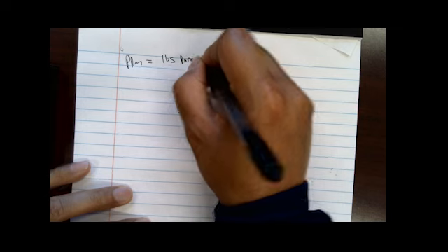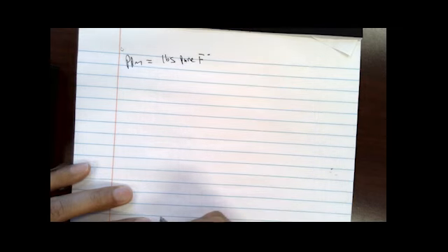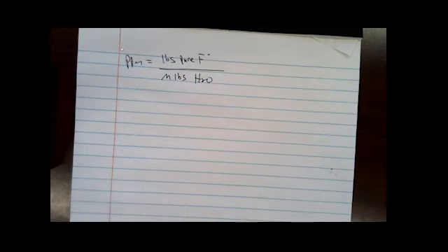Let's first start again by converting our water into million pounds of water, and also by finding how many pounds of pure fluoride chemical we are using, right? So let's go to the formulation sheet. We know we're using the part per million equation right here. Let's write that down. Part per million is equal to pounds of chemical, in this case pounds of pure fluoride ion, divided by our million pounds of water. And again, the question is asking what is the concentration in milligrams per liter of fluoride ion?